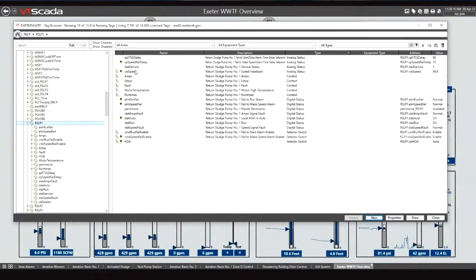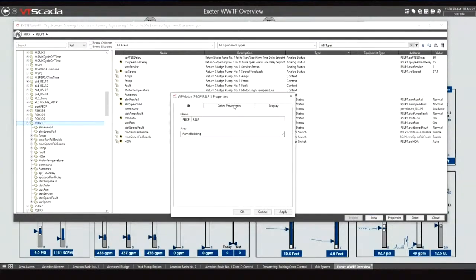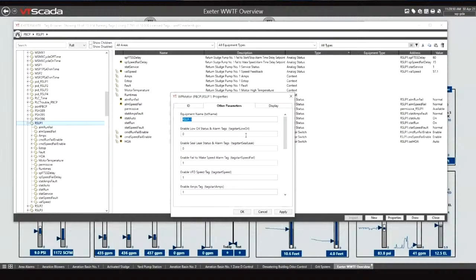We have other children inside of this. So we're getting all of this information in here by a simple tag name, RSLP1. As long as we have that same data structure and that same tag in the PLC, we get all this data in one fell swoop. The other thing we've done is added parameters to help configure this tag.